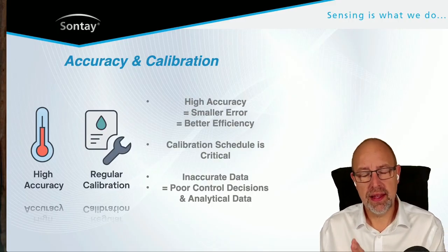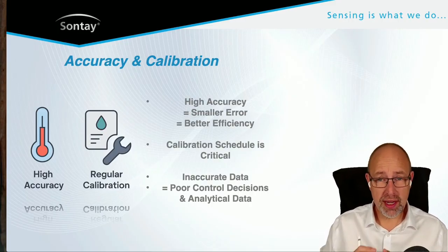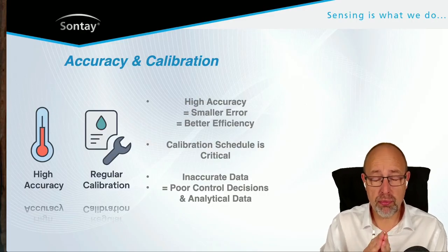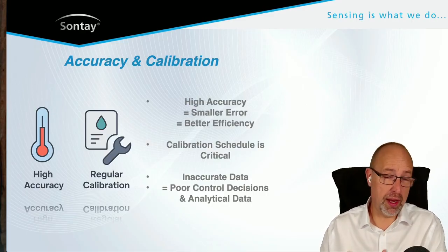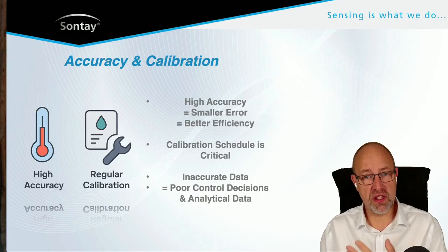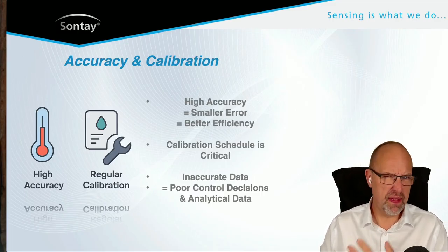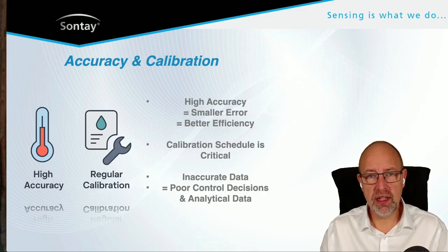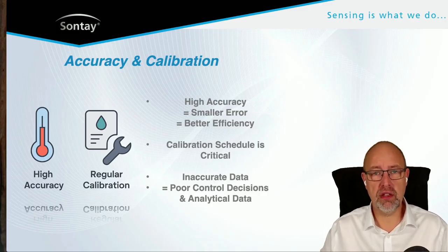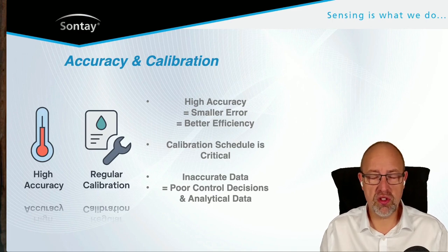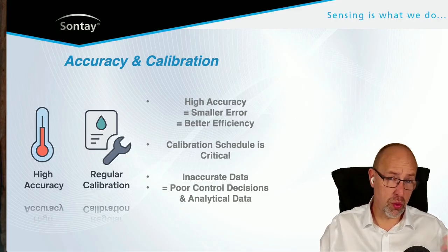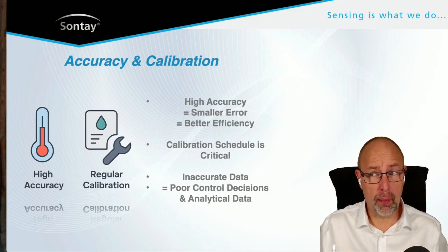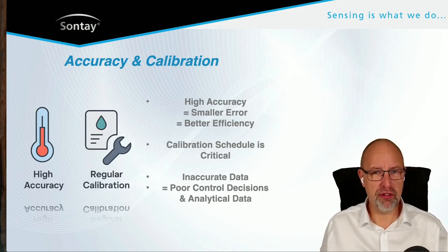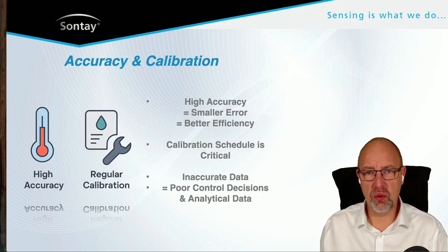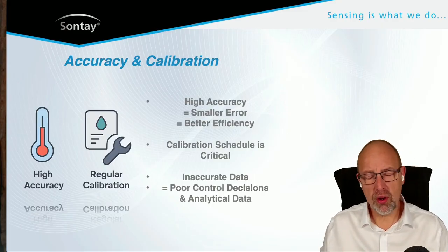Although we don't need that same level of close control, so we can have a broader range of temperature fluctuation, whereas in a semiconductor plant a 0.05 degree C difference could have a significant impact. That wouldn't affect a data center, but we still need accurate information - if you don't have accurate sensor information, how are you going to control this space? Again, it's unlikely in a data center that a fluctuation of 2 degrees C is going to cause all your servers to melt down. It could, if you're running it right to the wire, but you'd have to be pretty bold to run it that close. But 2 degrees C probably won't affect you.